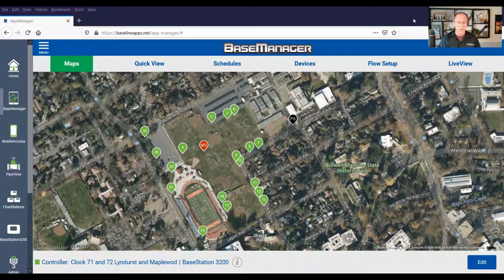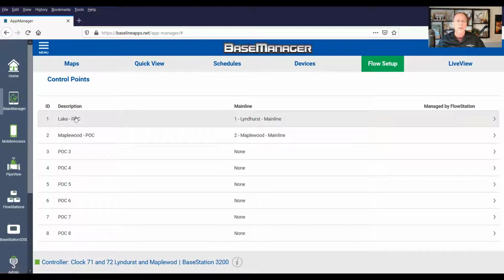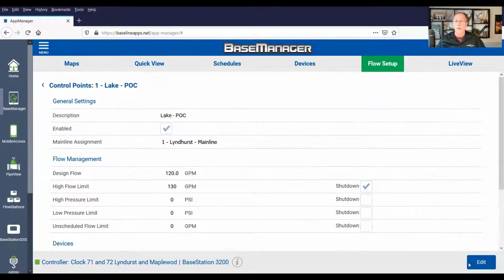So the other thing to look at is maybe the limits in Base Manager are not accurate. I'm going to assume that the devices are assigned and set up correctly, that you've assigned your flow meter, that you've assigned your master valve, that you've got the right K value in there for those, that those are dialed in. If that's not the case, that's another dive into that one. So we're going to go in the flow setup and then open the control points. We're going to look at this first control point. I'll open that one up and then click Edit.